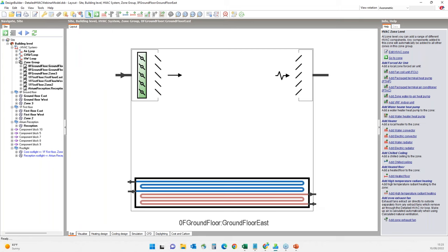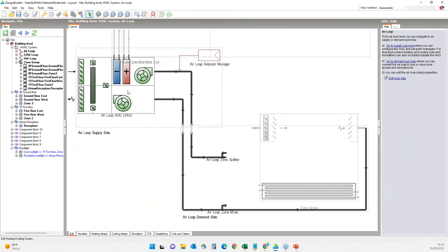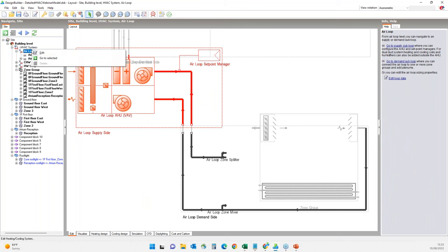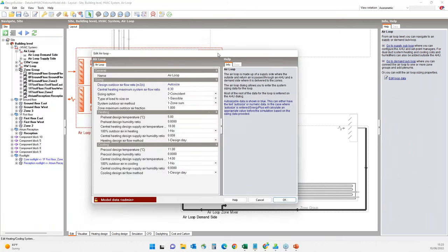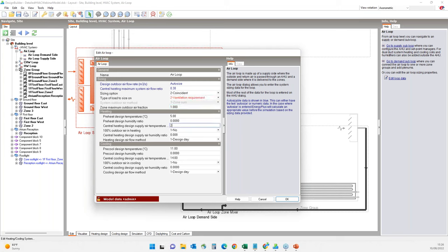I'll go to the air loop and modify its configuration. On the air loop edit dialog I'll change the load type from sensible to ventilation requirement, as this air handling unit will now only precondition the fresh air. I will also change the design supply air temperature for heating to 22 degrees and for cooling to 18 degrees, because we don't want the ventilation air to be too warm or too cold.